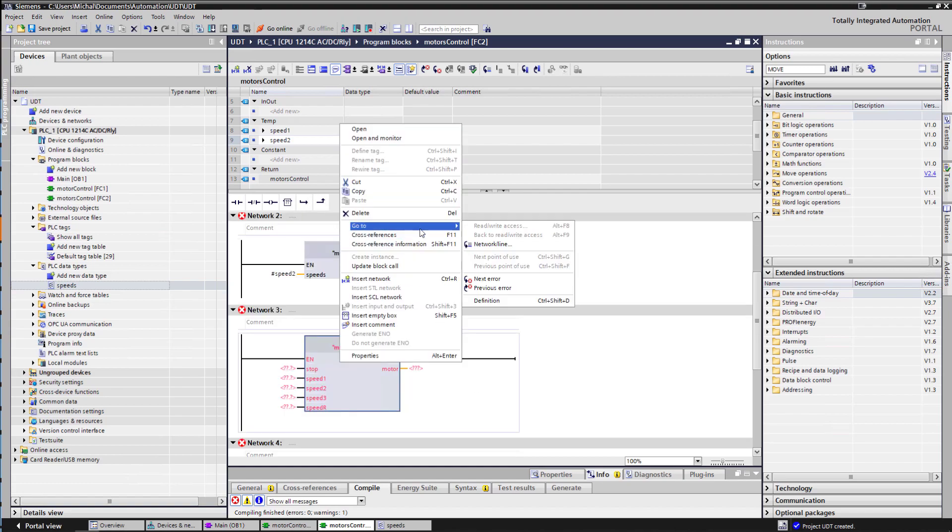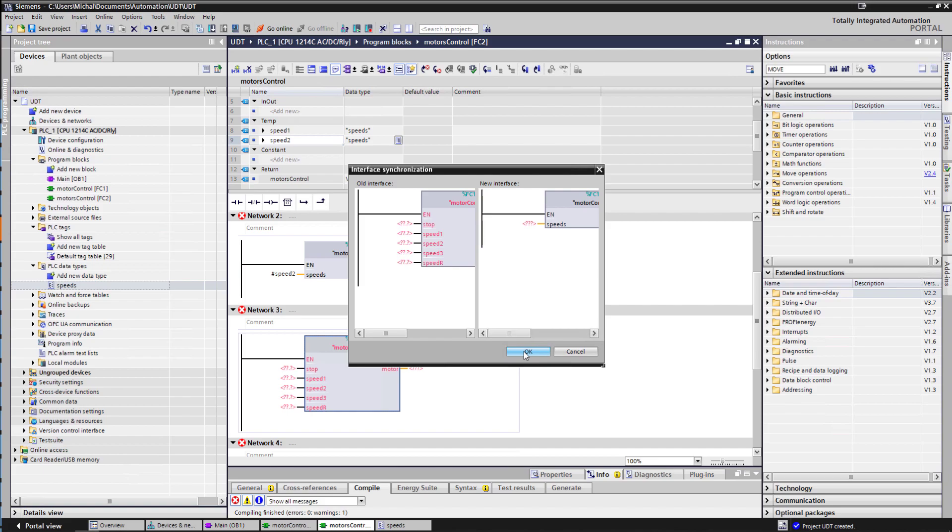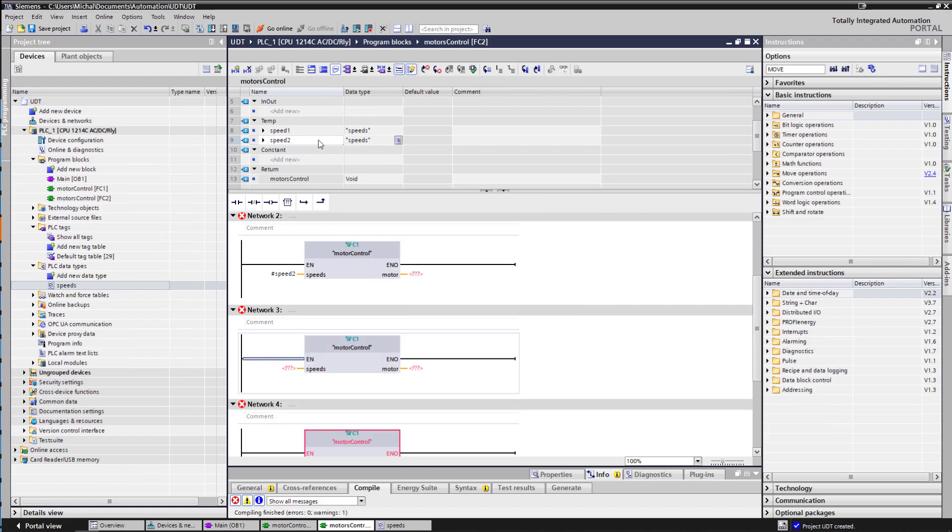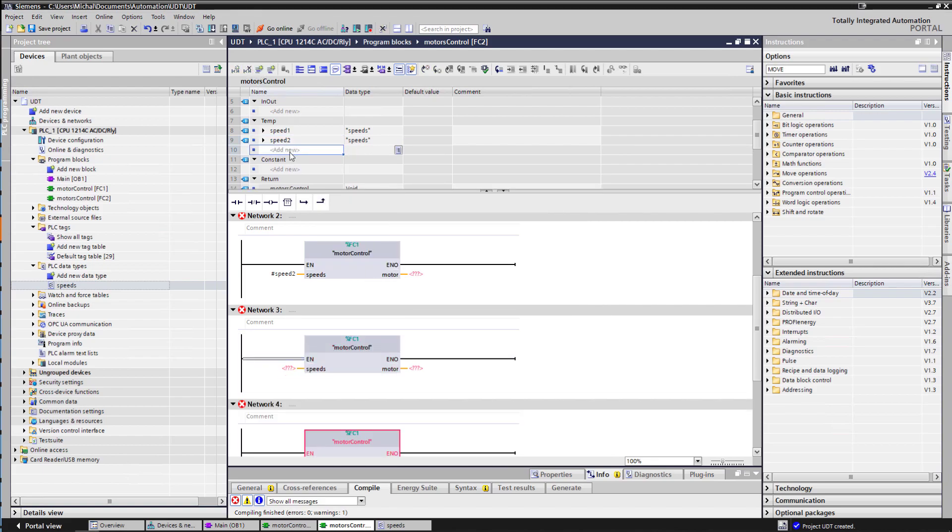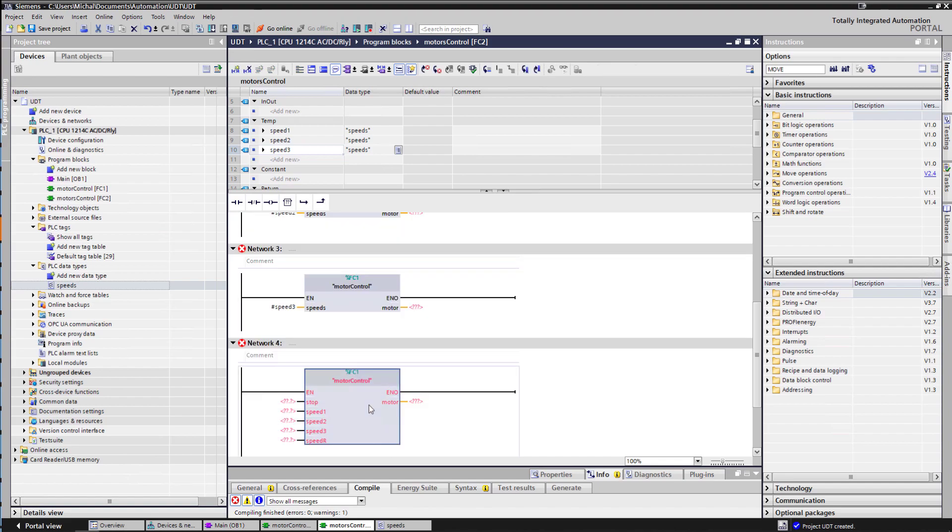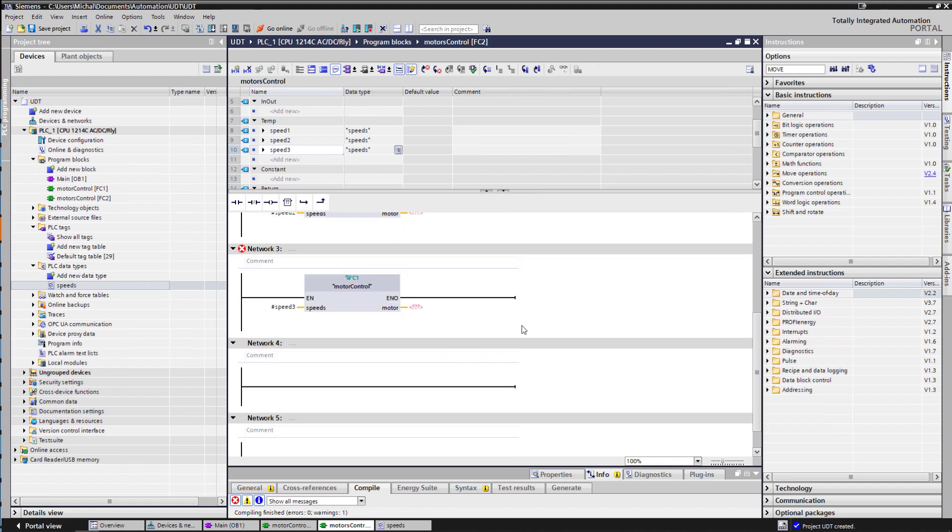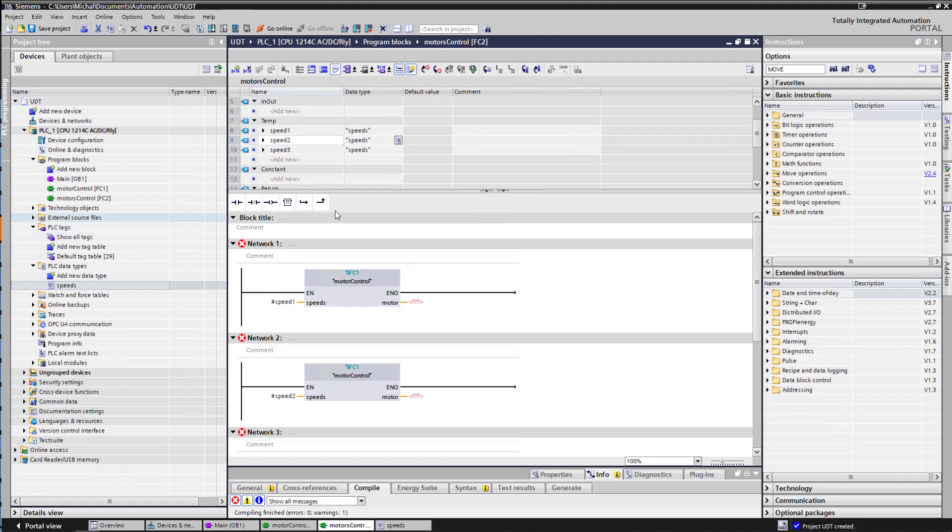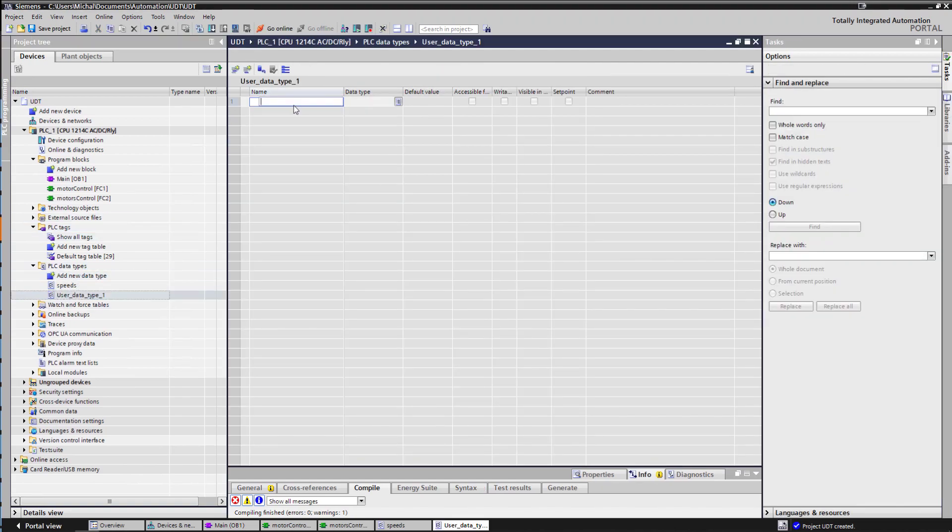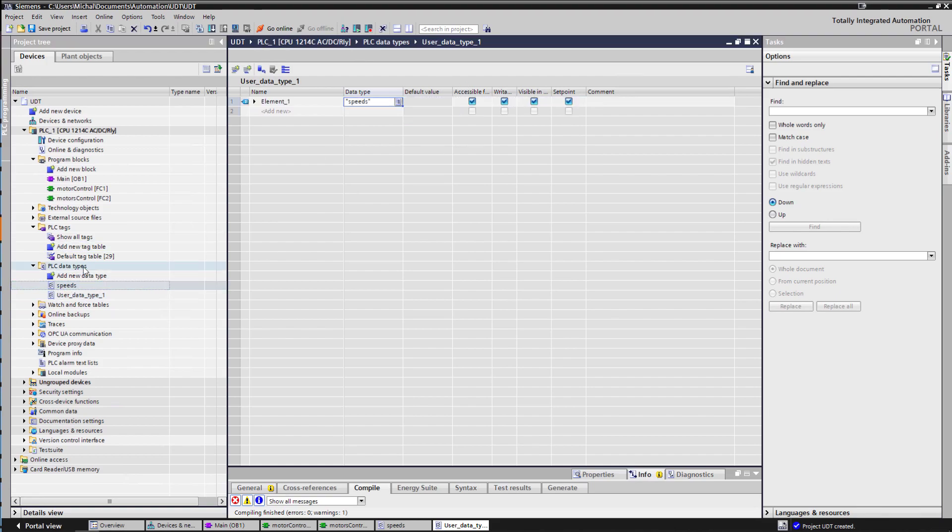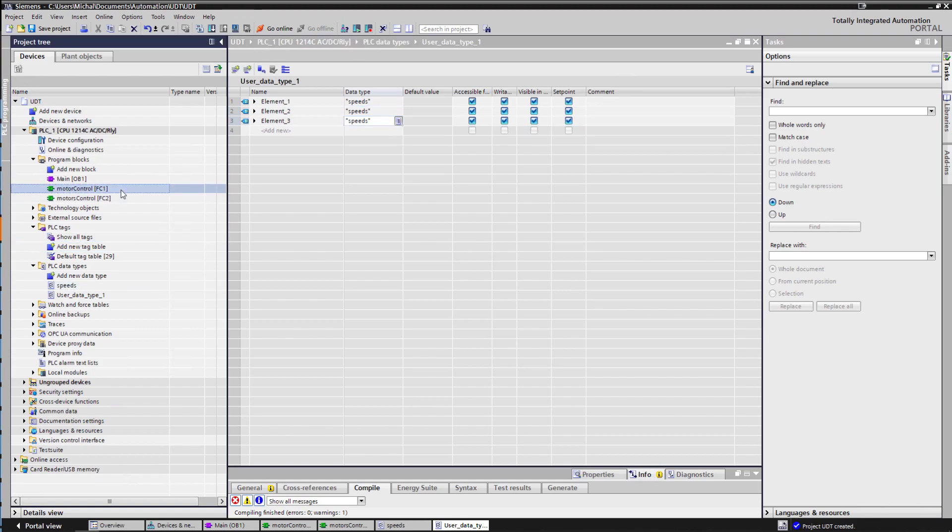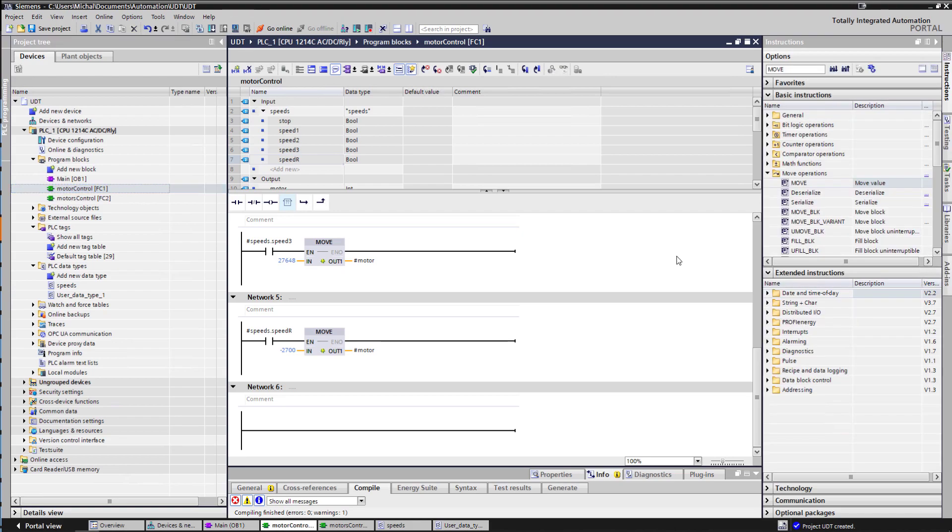And I can have then the speed for my third drive. And I don't need to keep redefining all these things. It just makes my life easier. And again, we can have UDTs encapsulated in UDTs. So if I had a high-level block that takes multiple of these, I could make a UDT that has a few UDTs inside. So you can start encapsulating and encapsulating the encapsulation.